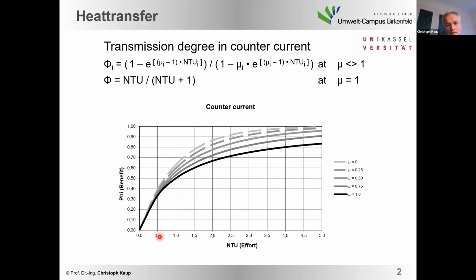NTU is the number of transfer units, which is a dimensionless value describing the heat exchanger. It is nothing else than the U value, the thermal efficiency of the heat exchanger, multiplied with the surface of the heat exchanger, based on the airflow which we would like to heat up or cool down. So if we take, for example, an NTU of 1, that might be a round coil with 8 rows, for example, 100 Pascal pressure loss, and, I don't know, 10,000 cubic meters per hour, then this is a physical law that will lead us to an efficiency of the heat recovery system of 50%.